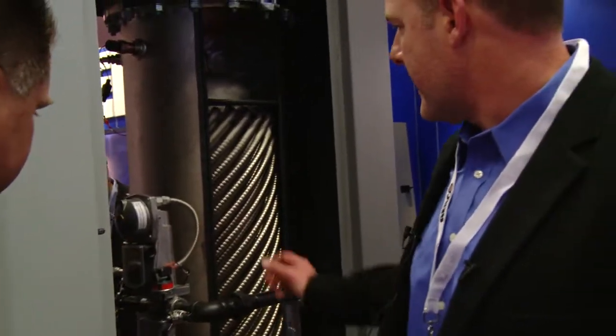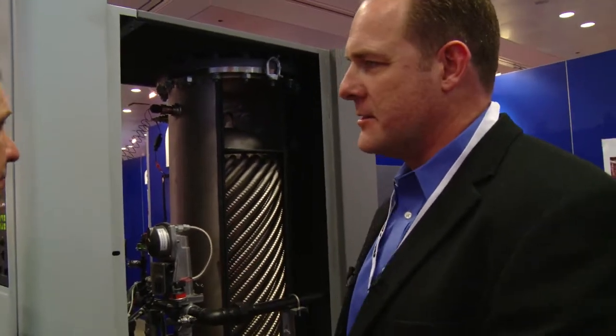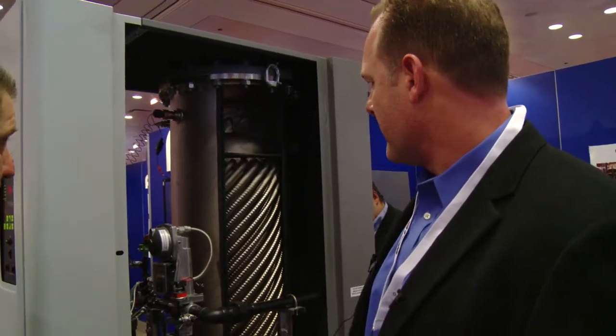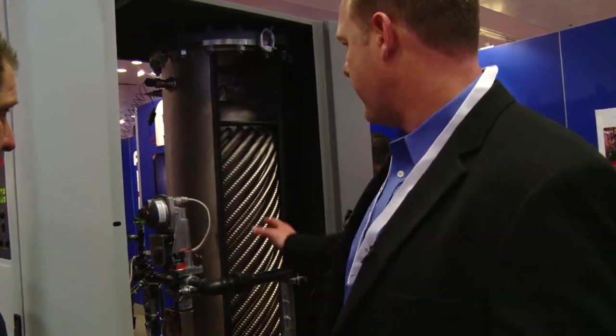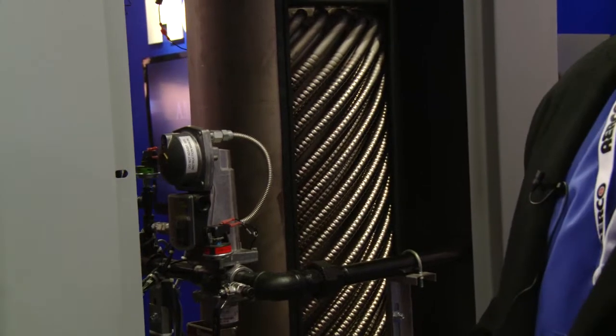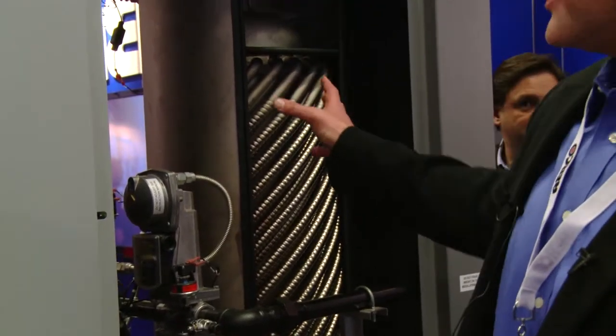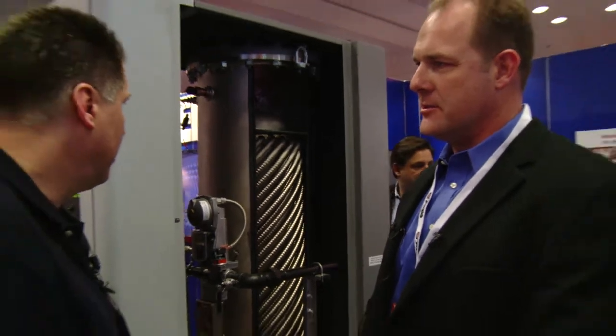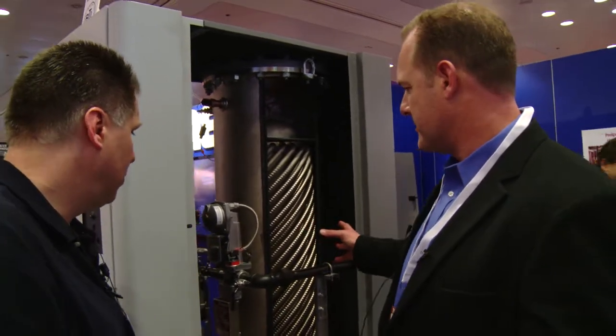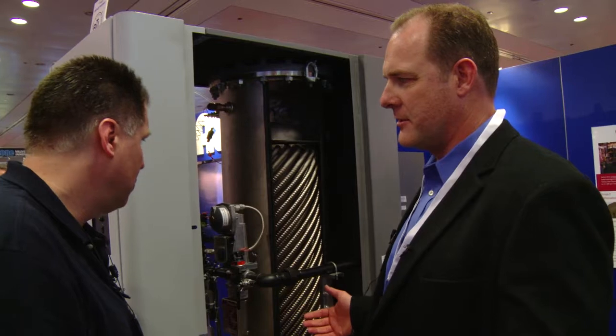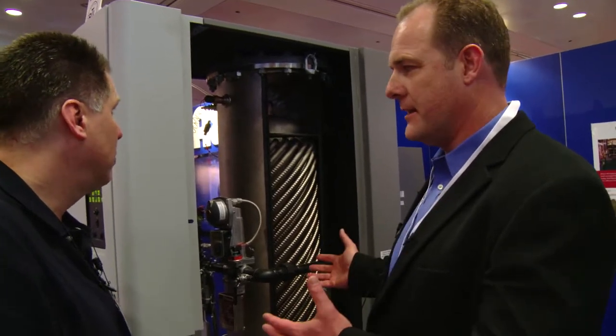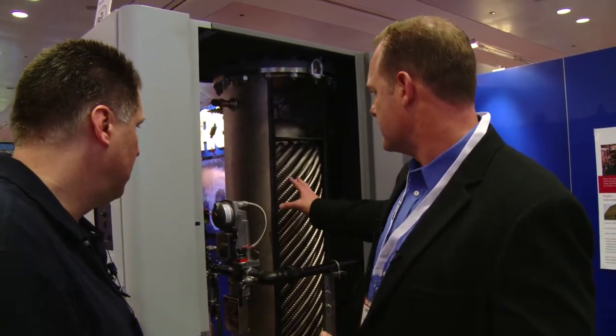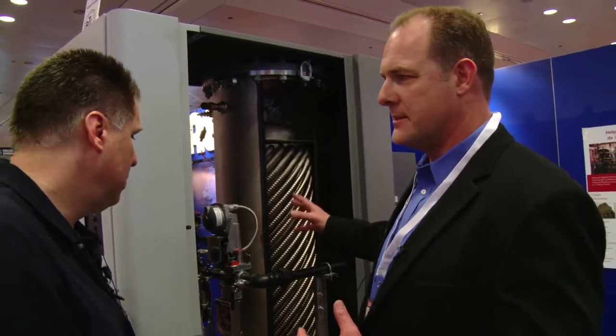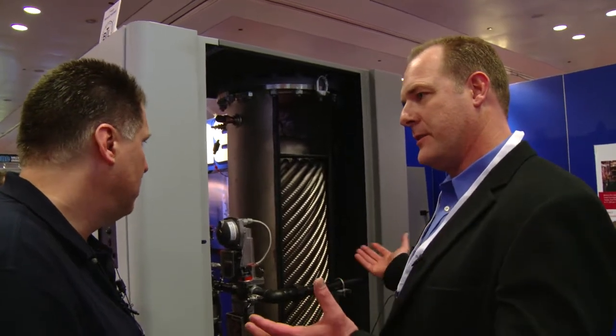Very unique. AERCO's had about 15 years experience with stainless steel manufacturing in our Benchmark boiler, and we've adapted that material into our Innovation product line. This is a fire tube, 316L stainless steel heat exchanger, so the water is in the shell and the combustion gases are in the tubes. This offers the flexibility to not have a continually circulating pump between the tank and the heat exchanger, and allows the heat exchanger to expand and contract with the thermal stresses and not require the constant flow of a pump or the constant temperature that you would keep in a large storage tank.